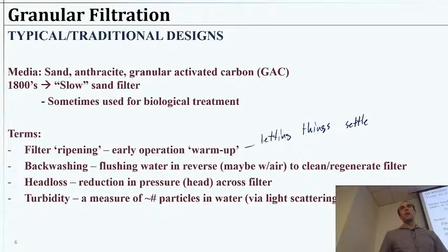It doesn't really matter what kind of particle. My bubbles didn't stay very long, so it's no longer turbid. But while I'm shaking it, certainly there's a lot of light being scattered by the bubbles. So that's a measure of our particles. So we can monitor and say, okay, if we ever have a lot of particles escaping our filter, we know, hey, alert, it's time to stop. Because the filters will fill up, and eventually particles will start making their way out when we have too many.